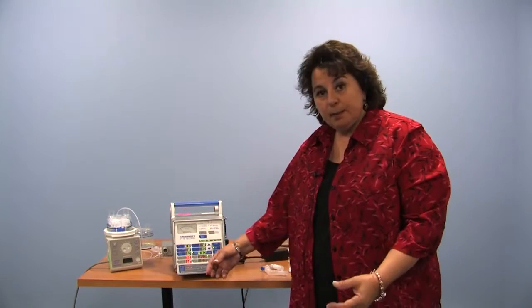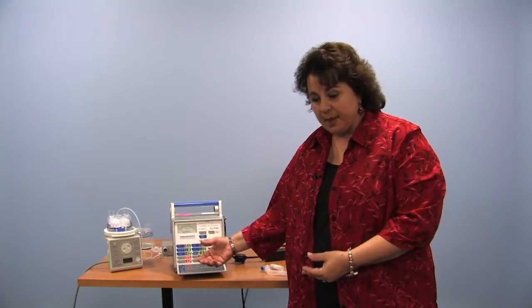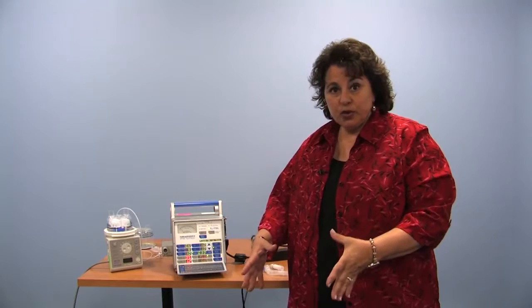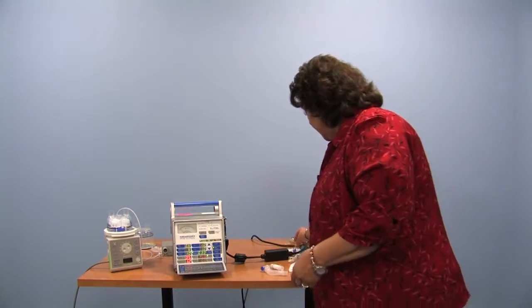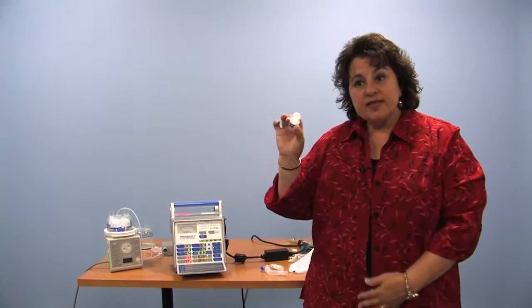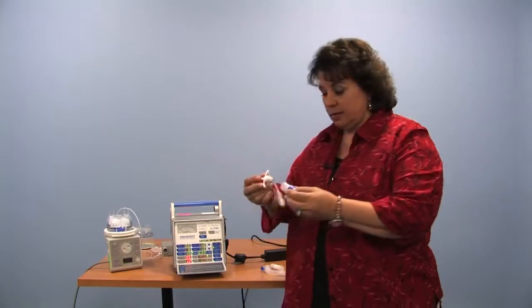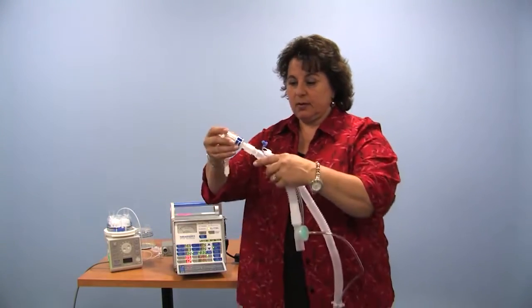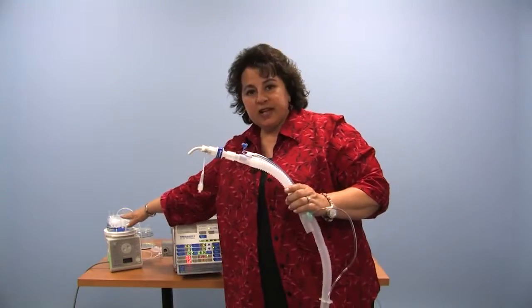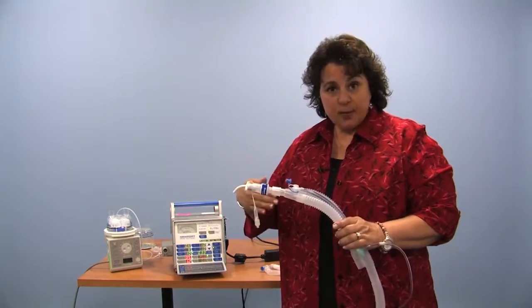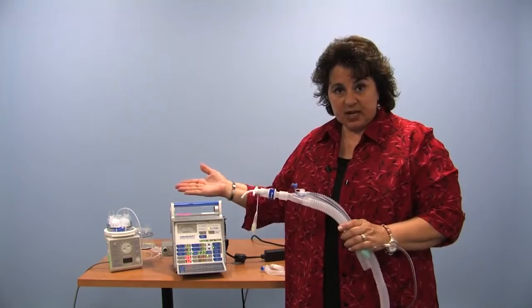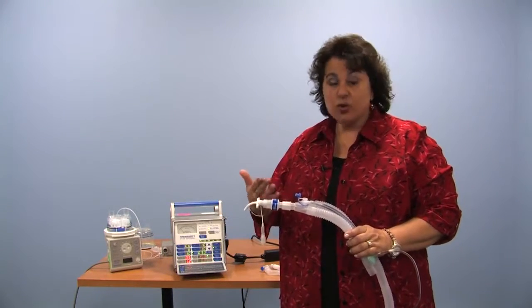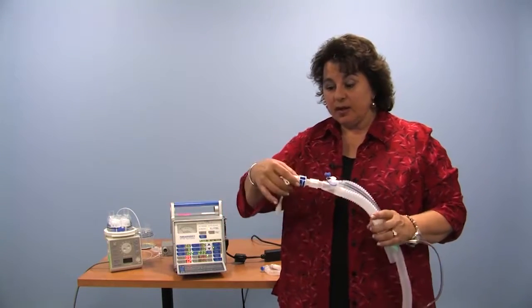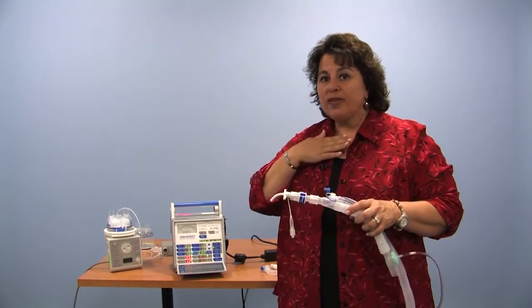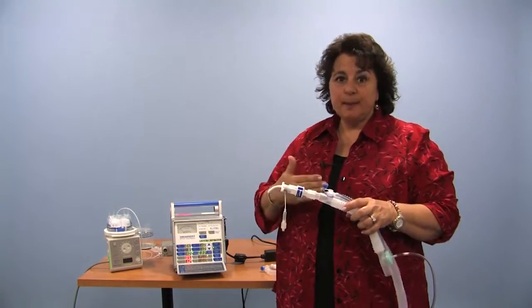What I'd like to do next is put hoses onto the machine to show you how we connect them. We have both the dry circuit that you use when you go out of the home, or if you're just using the HME or heat moisture exchanger. Some young adults and adults only use the heat moisture exchanger to their tracheostomy tube and to their ventilator. They do not necessarily all use the humidification system. Smaller tracheostomy tubes, younger, smaller patients, we do recommend that they use heated humidification. Larger tracheostomy tubes, larger, older patients don't always use the humidification. They rely on the heat moisture exchanger to capture heat and moisture when they exhale through their trach tube and provide it to the air that they breathe back into their lungs.